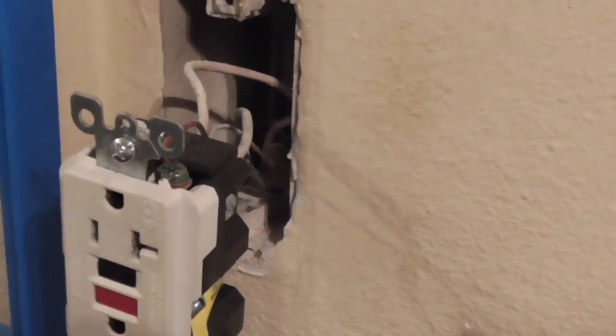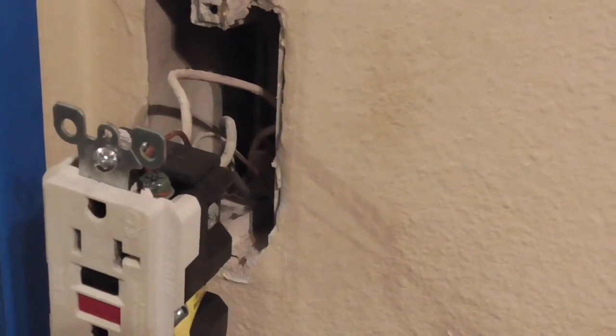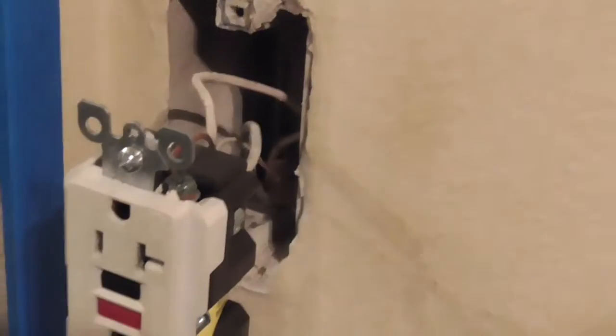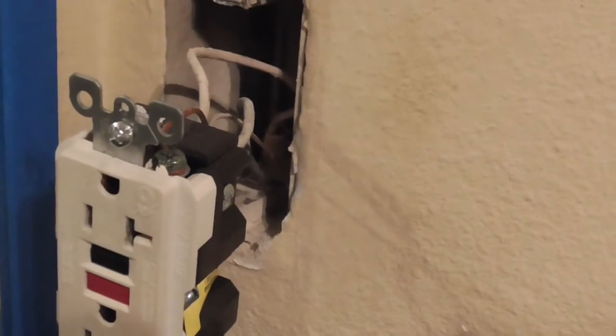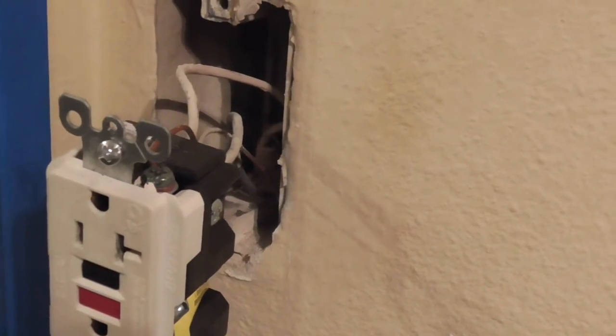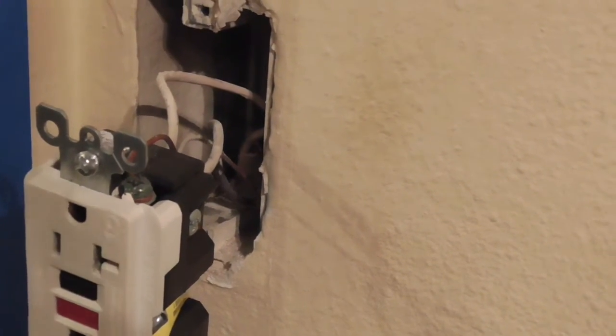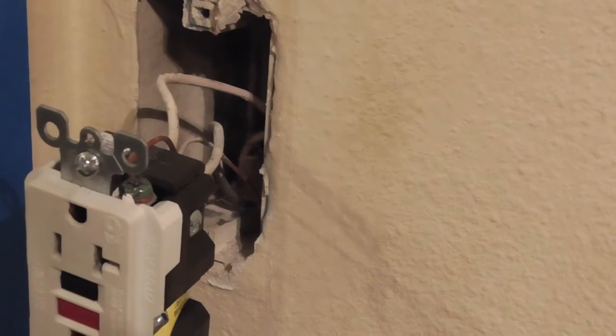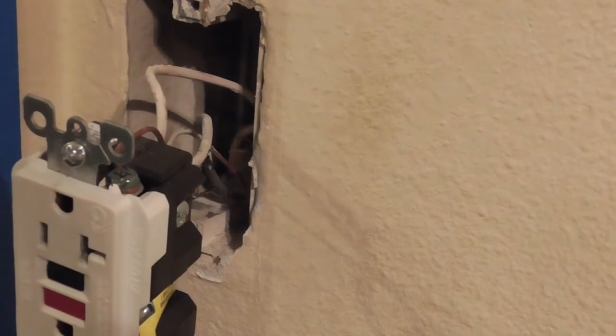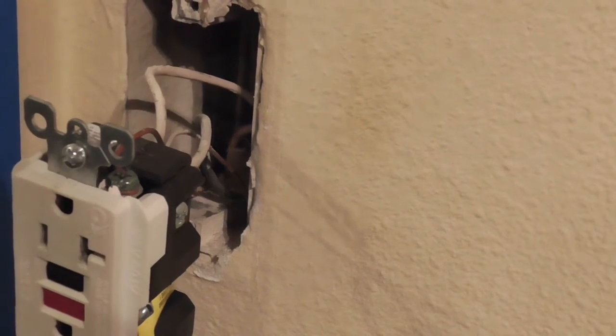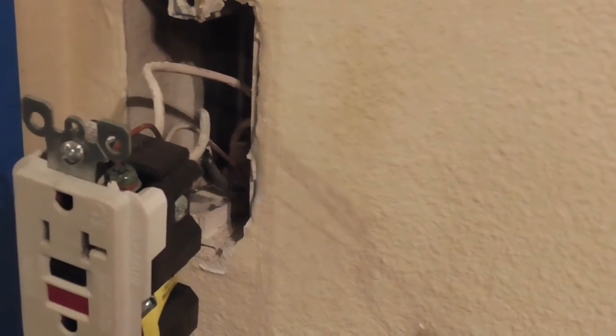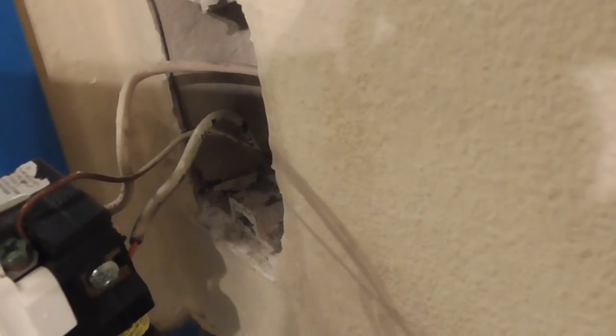And you can see that when they installed it, they put the little ground tab up at the top. Normally it's on the bottom. It really doesn't matter how you install it, as long as you install the wires the right way. But what they did is, had they positioned this in the right direction, the wires would have been okay. So all I'm going to do is take the wire off, I'm going to leave the ground wire alone that's on the top. I'm going to reverse the two, I'm just going to take the two wires off, turn the outlet upside down, put the wires back on, and everything should be okay. We'll find out in a minute.